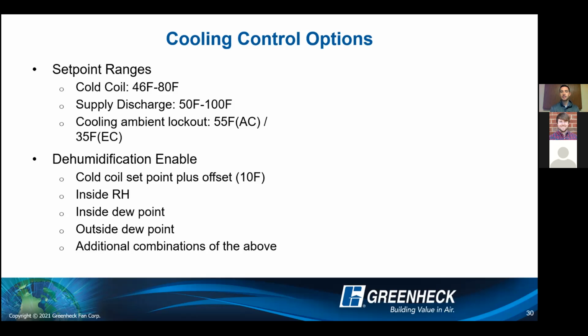If you didn't like enabling dehumidification based off of that sequence, you can look at the indoor relative humidity. You can look at the indoor dew point if you wanted to and had the appropriate sensors, or even the outdoor dew point at that time as well. So a lot of different ways to look at when we want to enable dehumidification. And then there's also additional options to utilize a combination of the above, where it might be inside dew point or inside relative humidity, things like that.